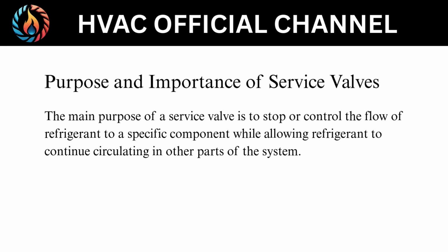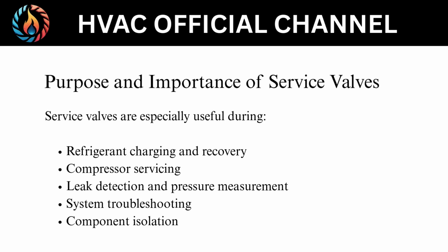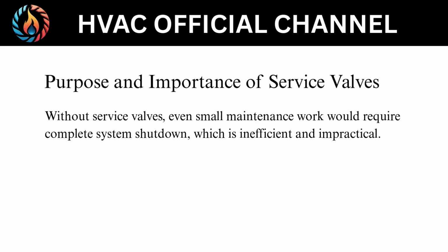Purpose and importance of service valves. The main purpose of a service valve is to stop or control the flow of refrigerant to a specific component while allowing refrigerant to continue circulating in other parts of the system. Service valves are especially useful during refrigerant charging and recovery, compressor servicing, leak detection and pressure measurement, system troubleshooting, component isolation. Without service valves, even small maintenance work would require complete system shutdown, which is inefficient and impractical.